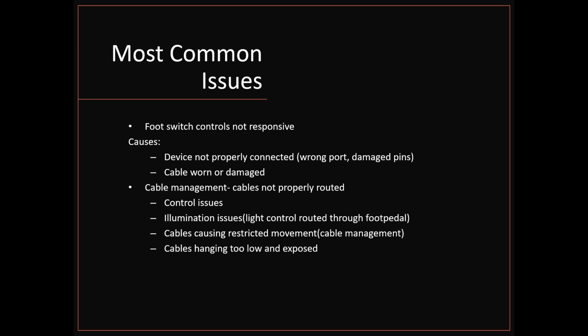Foot switch controls are unresponsive. On ophthalmology scopes and plastics, hand plastics, neuro, some of the spine folks will use a pedal at different times, but you'll find that you'll have unresponsive functions. That could be a whole number of things. It could be that the specific way that pedal is configured for that surgeon has something messed up, or it's not on that specific surgeon's profile. Each surgeon can have every button of that pedal perform a certain function, and they can customize that. They'll always have your standard user function, and then you can put in the specifics for the surgeon.